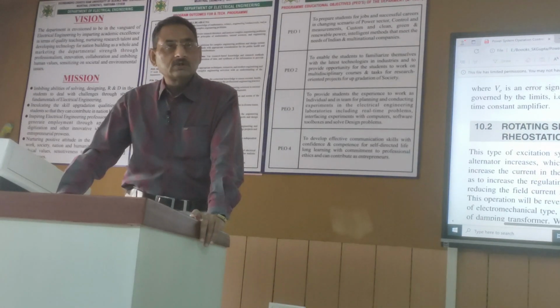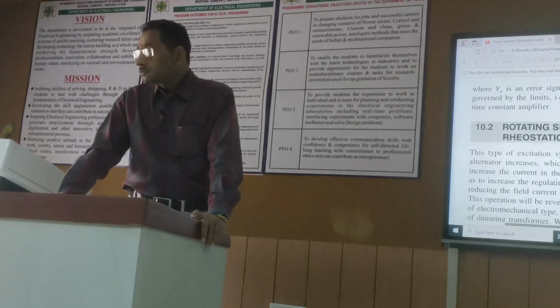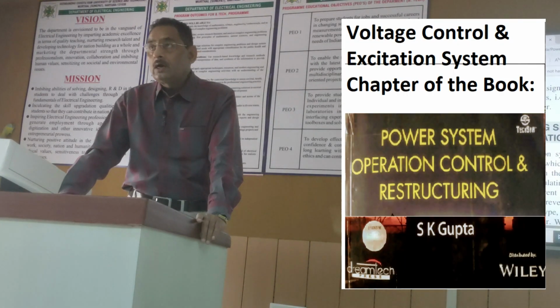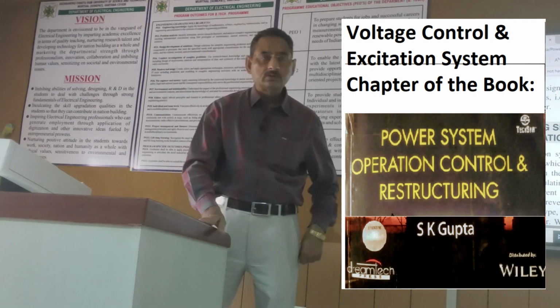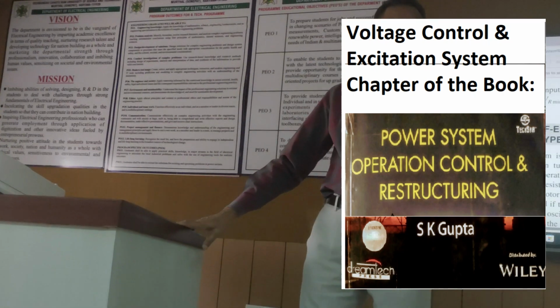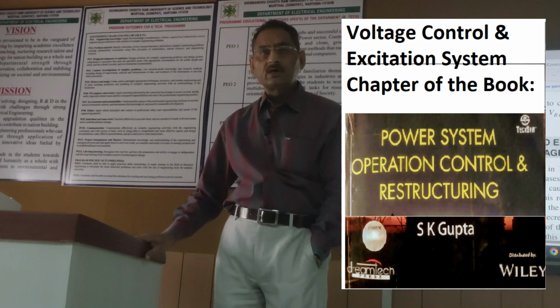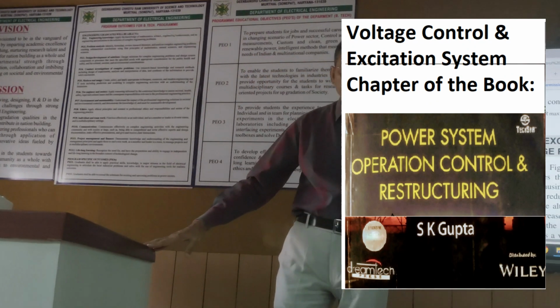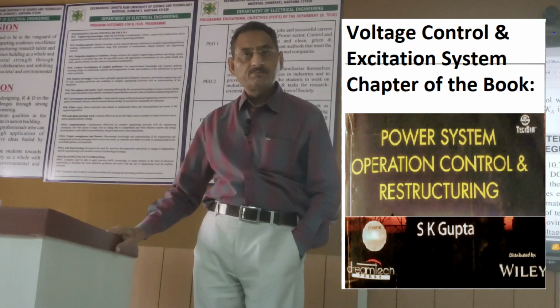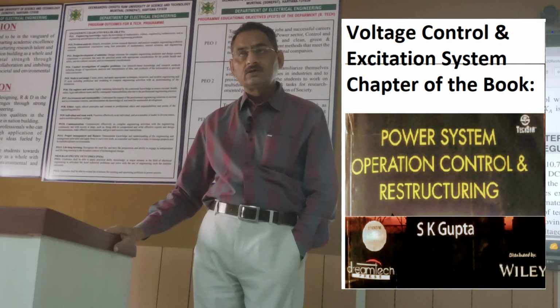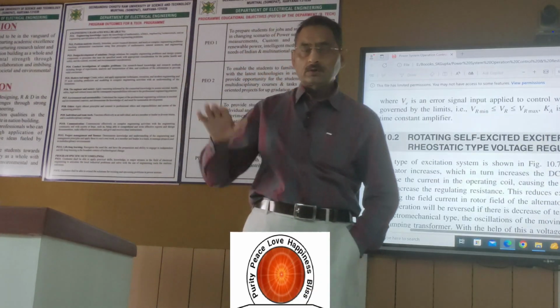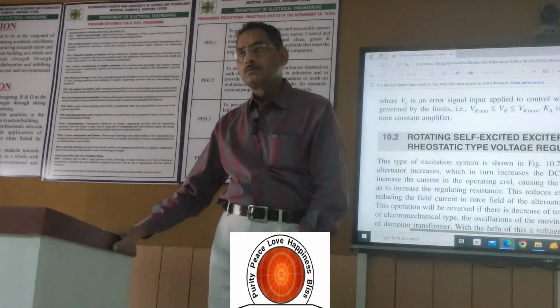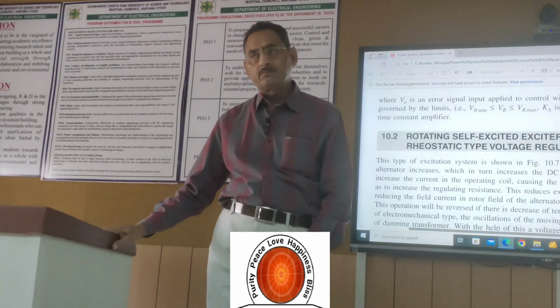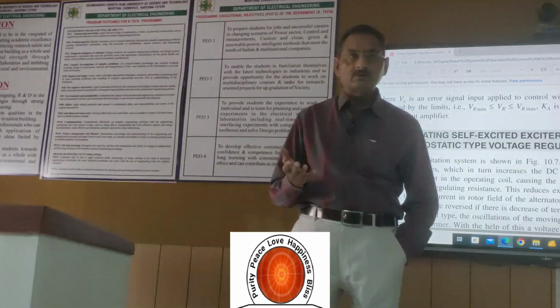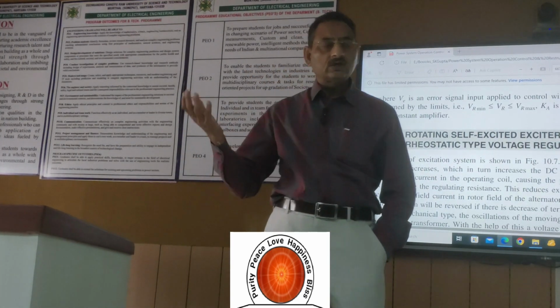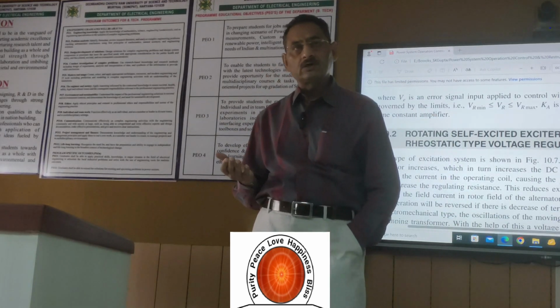So far in the previous classes we described one of the excitation systems, and after discussion we reached the conclusion that it is the reactive power that is mainly responsible for the voltage of the system. If the reactive power supplied is less than the reactive power demanded, then voltage becomes less than the standard value, that is the 1 per unit value. And if the reactive power supplied is more than the demand, then voltage goes above the standard value, that is the 1 per unit.